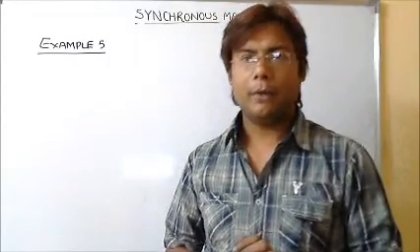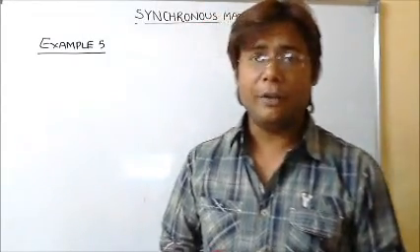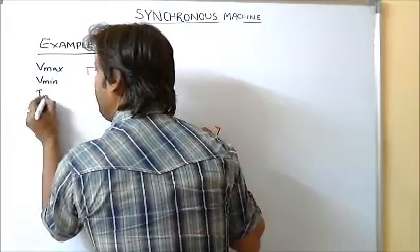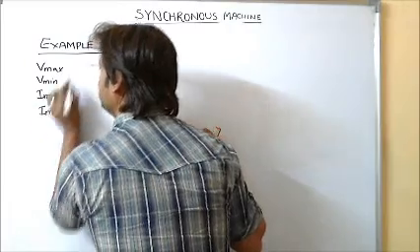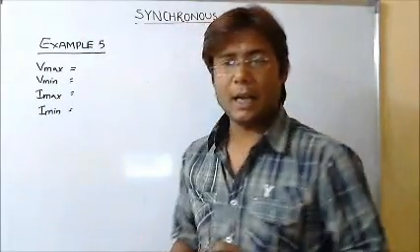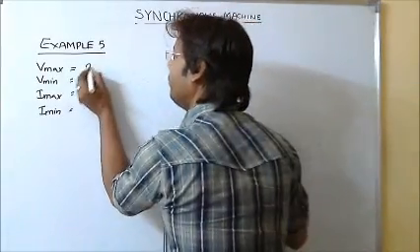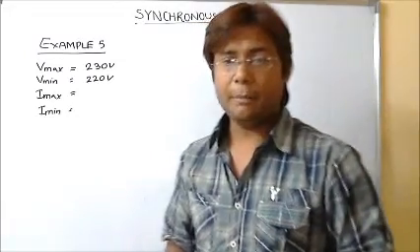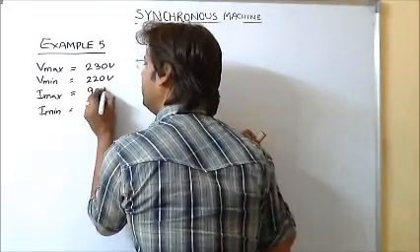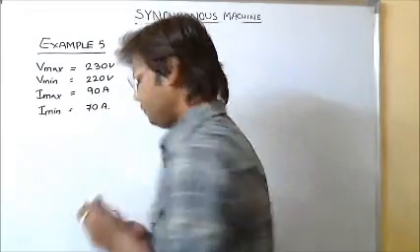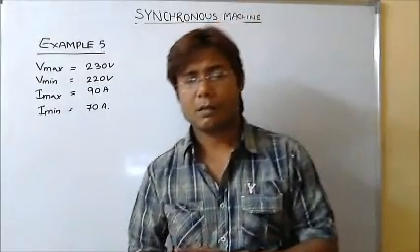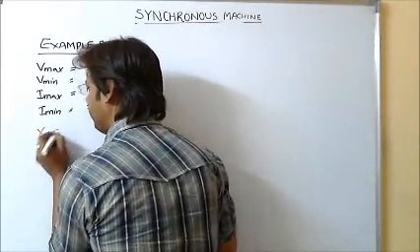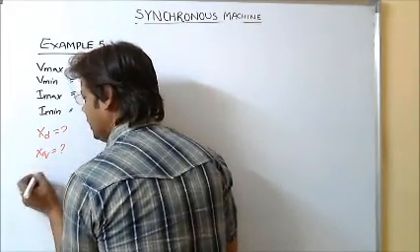We can go to Example 5, in which Vmax and Vmin are given, as well as Imax and Imin. The values are Vmax = 230 V and Vmin = 220 V, with maximum current of 90 amperes and minimum current of 70 amperes, for a synchronous machine under a slip test.